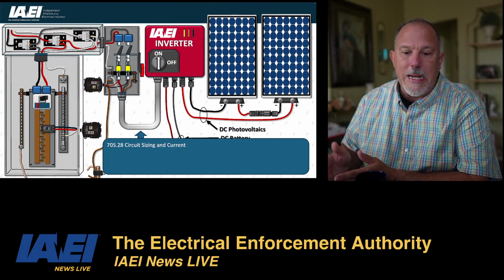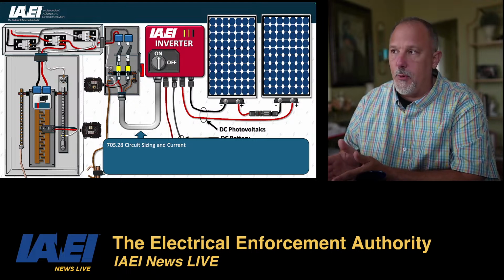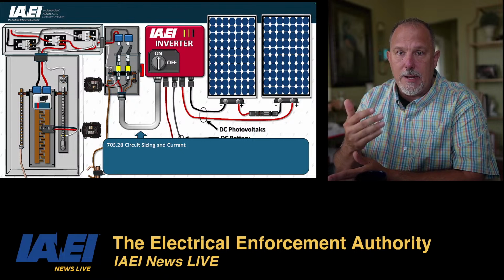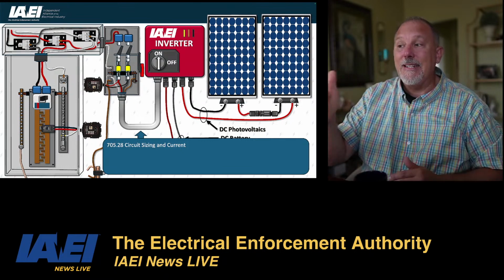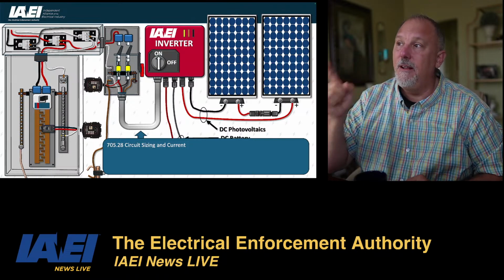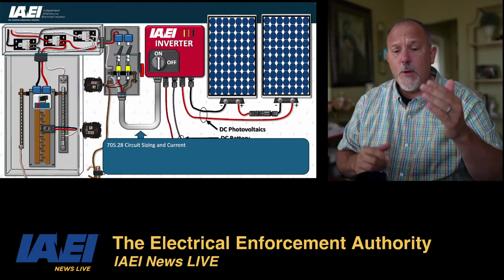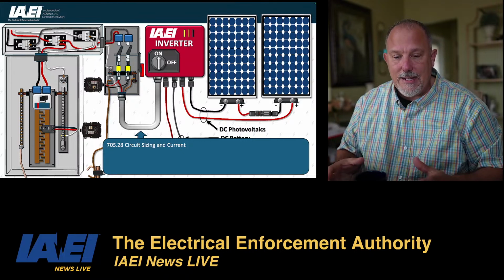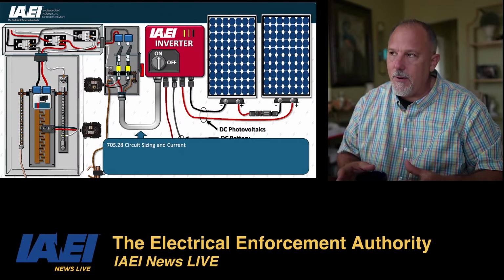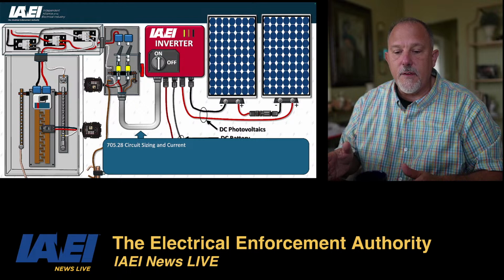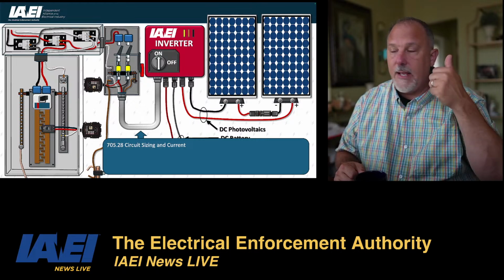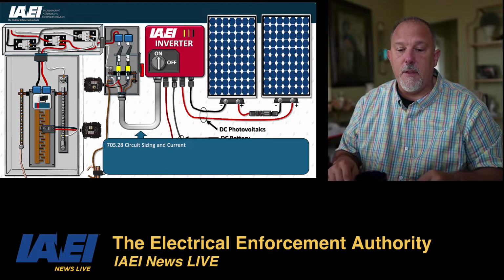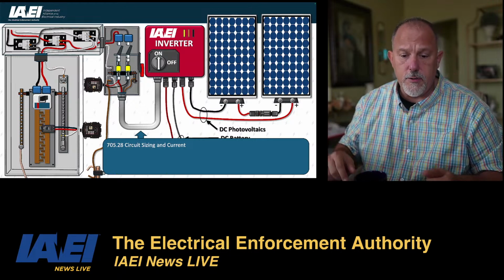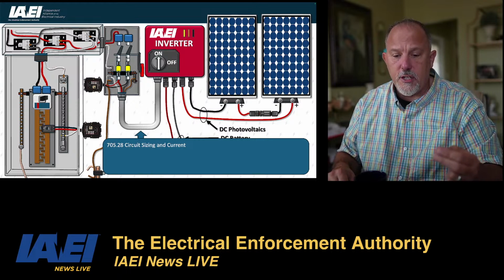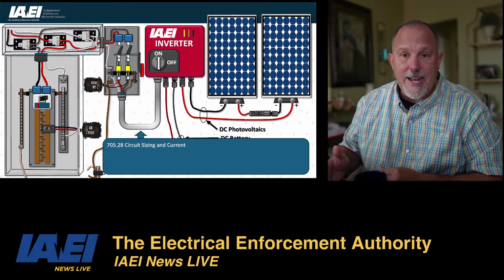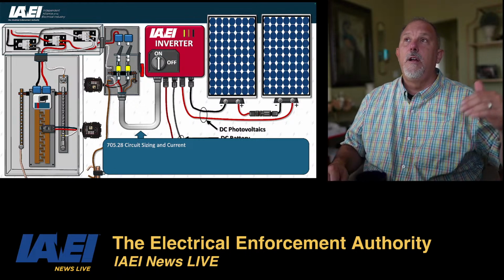So what 705.28(A), power source output, says, because that's a power source and it's an output, is that I size these conductors, not for short circuits, but for how much energy or how much current that inverter can put out. So in 705.28(A) you get guidance on how to calculate that. It says your power source output has to be calculated using one of three methods. It's either the sum of the continuous output current ratings of the power production equipment, because I could have multiple inverters. Two, for power production equipment controlled by an energy management system, I use the setting of the energy management system, and that is a 750 article.